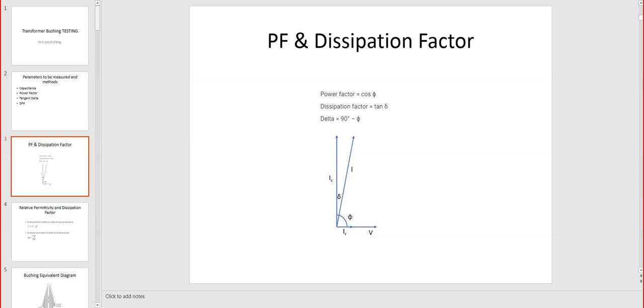Okay, last chance. Any other questions regarding the bushing testing? If not, I will just remind you that this is very similar to what you may hear from others. They perform on the insulators at least leakage current and tangent delta, power factor. Surge arresters, they perform kind of the same test, but they have different acceptable values. And on surge arresters you may also have functional tests, because they usually can support a certain discharge hundreds of times typically, but any test can actually shorten the life of the surge arrester.